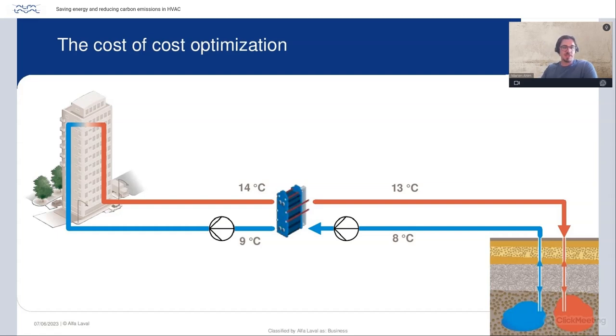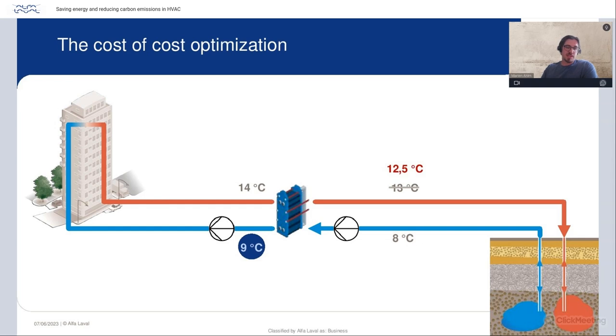If we look, the initial design was made like this: 8 to 13 on the well side, 9 to 14 on the building side. If you have a unit that is designed to deviate 0.5 degrees on the temperatures, what will happen in actual operation? The building side, the cooling loop for the building, will still need 9 degrees. The operating system of the cooling loop will ask for 9 degrees. And of course, to get those 9 degrees, you will have to run more water through the heat exchanger on the cold loop.